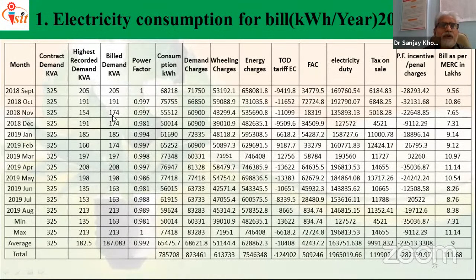Now instead of kilowatt hour, they have brought in kVA billing - kilovolt ampere - and kVA is always higher than kilowatt hour because of the power factor. So nowadays electricity bills get enhanced by 10-20% because of the power factor. These are hidden components we never bother about, and because of them the electricity tariff goes up by 10 or 12 rupees, depending on the type of consumer.